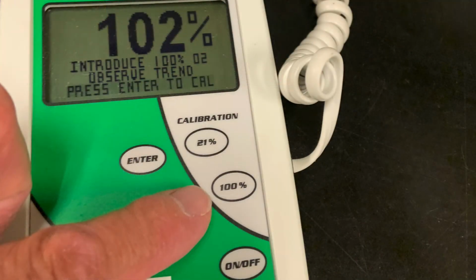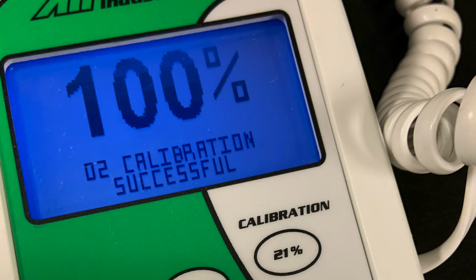Now press the 100% oxygen calibration button on the front of the analyzer. You'll see that the measured oxygen percentage will increase and then plateau or stabilize. Once it's gone as high as it's going to go, press the enter button, which will now calibrate or correct the analyzer to display 100% for what it's measuring. And you'll see here that we've successfully calibrated the analyzer. It is important to make sure that your probe is in a 100% oxygen environment when you do this. Otherwise, the analyzer will read incorrectly.